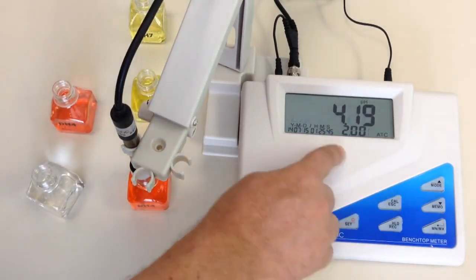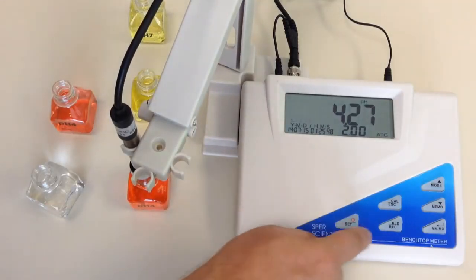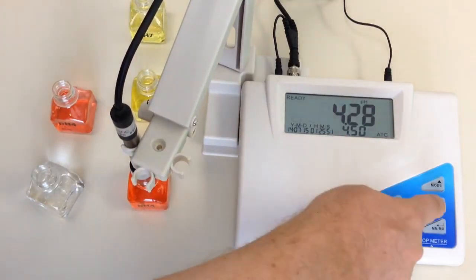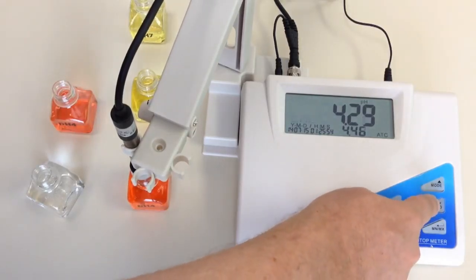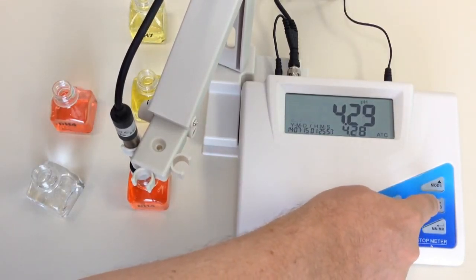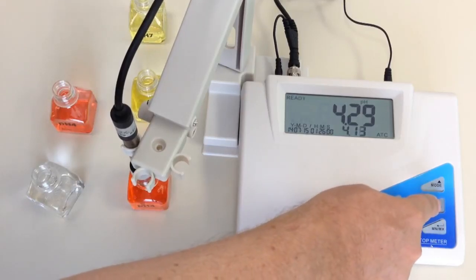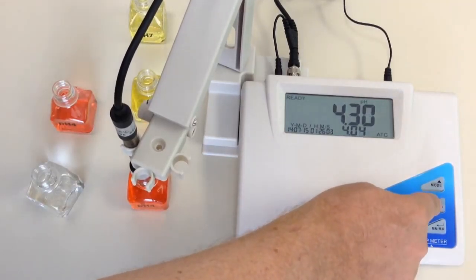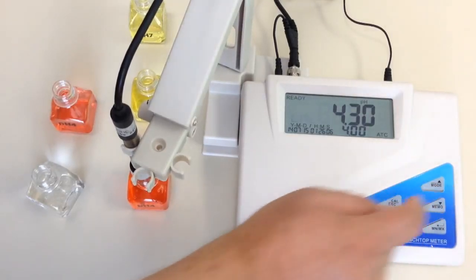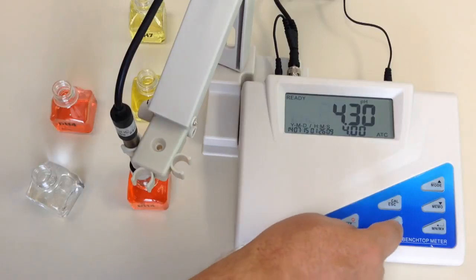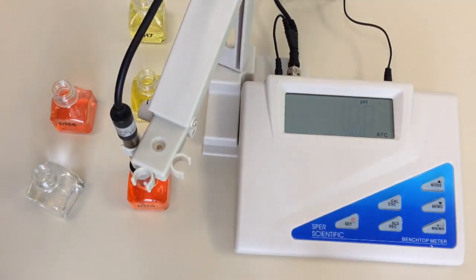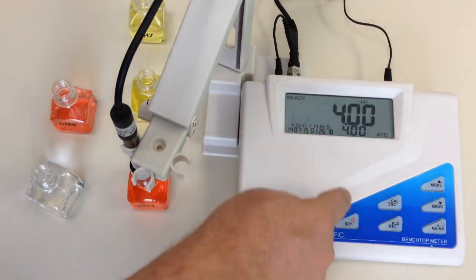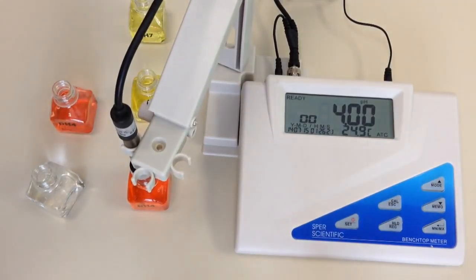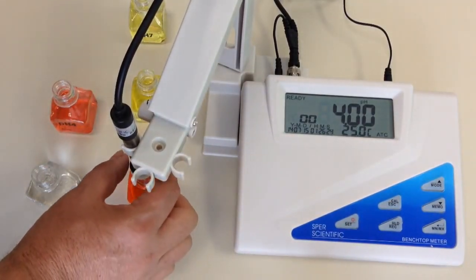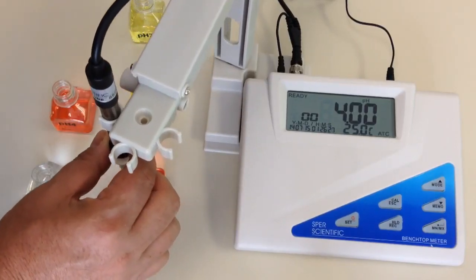So I'm going to hit the cal button. If you notice, the secondary screen here says 2.0. It's going to go to 4.50. I need to move that down by using the toggle buttons down to 4.0. Now reach 4.0, hit min-max, let it flash, then it stops flashing. Again, you got to be patient, let it do its thing. The ready appears, hit escape. It's calibrated to 4.0. It's as simple as that. And if you have any questions, please refer to your manual.